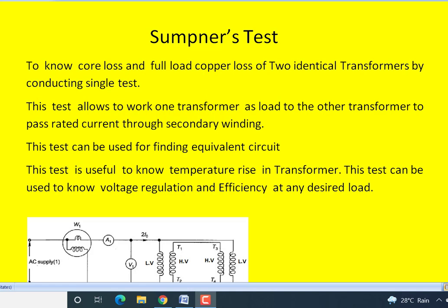But in Sumpner's test it is a different story. Here we take two identical transformers and we do only a single test on both the transformers to know the core loss and full load copper loss at once. This is the major advantage. Similarly, in the previous methods, that is individual OC test and SC test, we do not know the temperature rise, whereas here we can find out the temperature rise also.